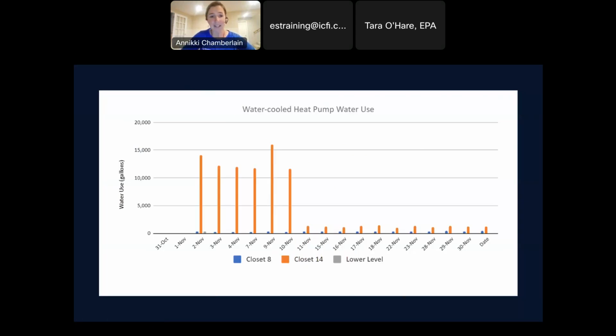That is because I'm a knucklehead, because I got a call one day and he's like, hey, that is way too much water compared to the other ones. So I had my guys inspect the valve. It was installed wrong. So boom, we were able to fix the valve, which seems obvious in hindsight, and drop the water use way down. This was just him walking around every day, putting it into a Google Sheet that did automatic calculations. So not only were we able to see where the problem was, we were able to verify that it was repaired.